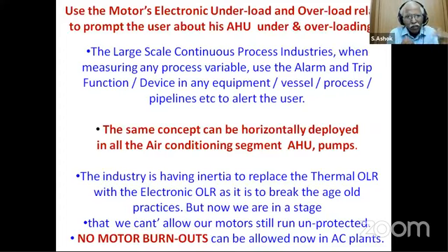So the large scale continuous industries have gone for an alert and trip mechanism for any of their process equipment as well as for the processes. Let us try to inculcate that practice in all our air conditioning installations, any of the ducted packages or any of the AHUs or the pumps where you are using. Instead of a thermal overload relay, go for an electronic motor protection relay, which gives an alarm for underload and can trip the pump or AHU on overload.